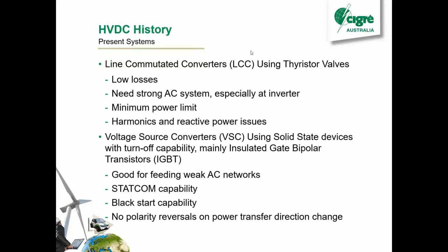And I'll briefly talk about voltage source converters. They're sort of the new kid on the block. They're utilising IGBTs, switching devices, so they've got turn-off capability. Because of that, they're good for feeding weak AC networks. They also act as StatComs. Each converter station can pretty much be a StatCom and help with regulating your AC voltage. It's quite the contrary to the LCC, which generally does bad things for your voltage. Voltage source converters can also do black start. You can't do black start with LCC.